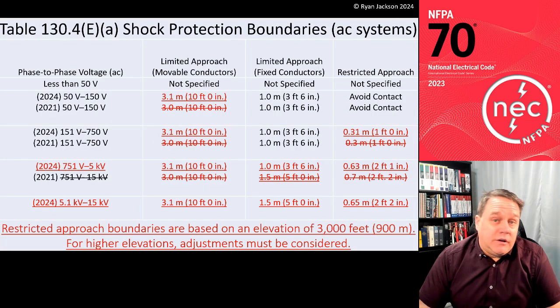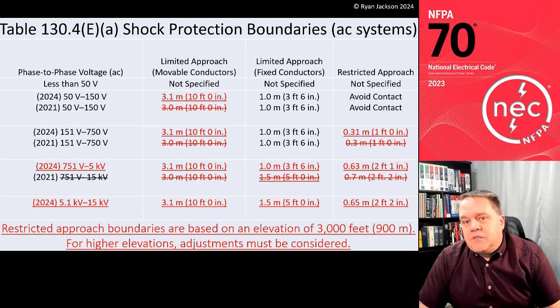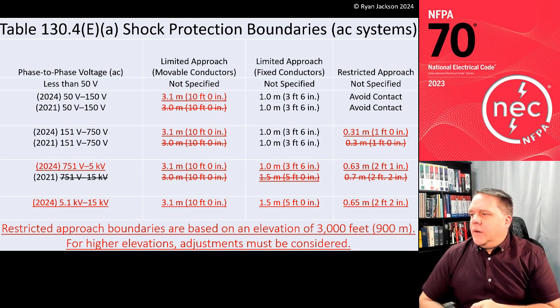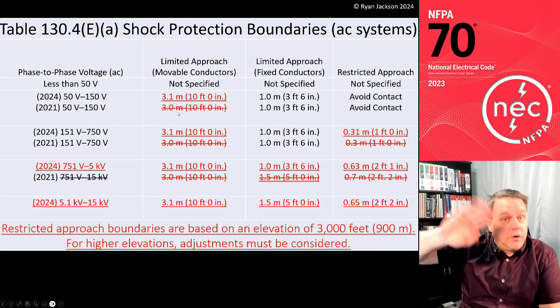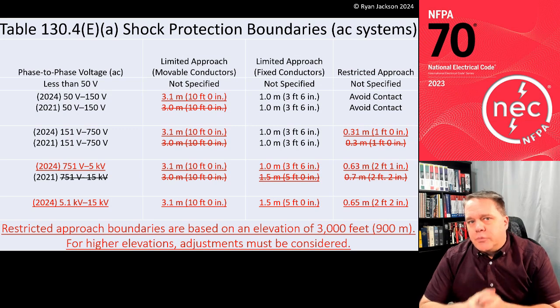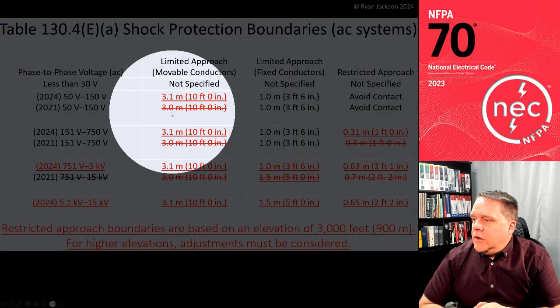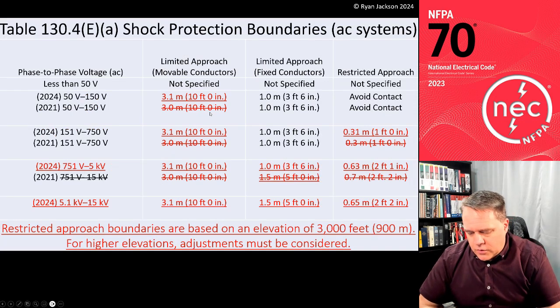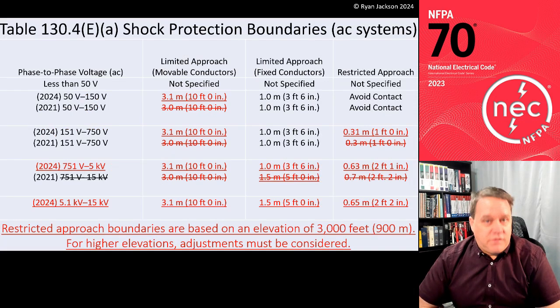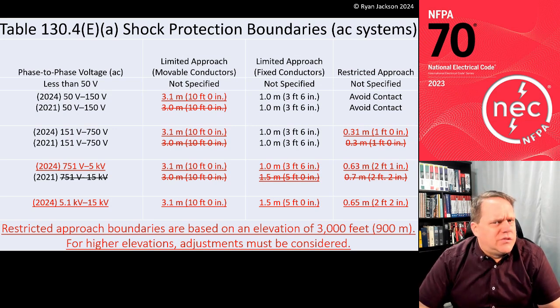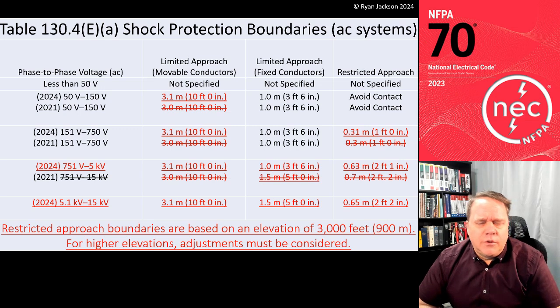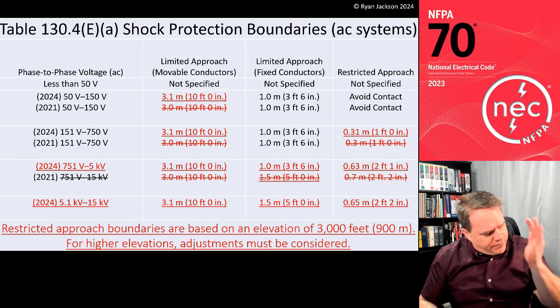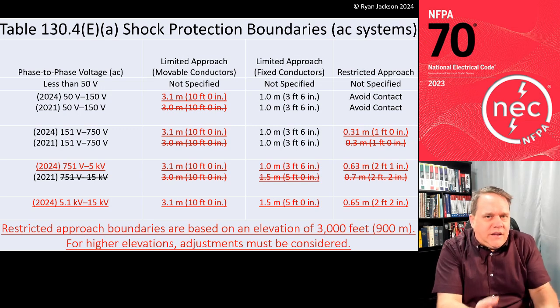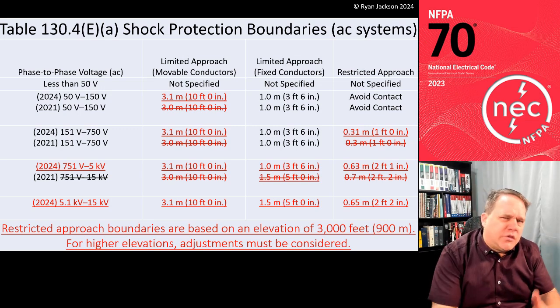Okay, this is kind of a frustrating one, but we had to change some of the electric shock protection boundaries. For example, if we open this up here, if we're looking at phase-to-phase voltage, limited approach for movable conductors, so maybe like an overhead line, something that moves around, in previous versions it said 3 meters or 10 feet. Well, 3 meters is not 10 feet. A meter is, I think, 39.3 inches, somewhere in that neighborhood. So very seldom are you going to have 3 meters and 10 feet. Yeah, horseshoes and hand grenades, that's fine.